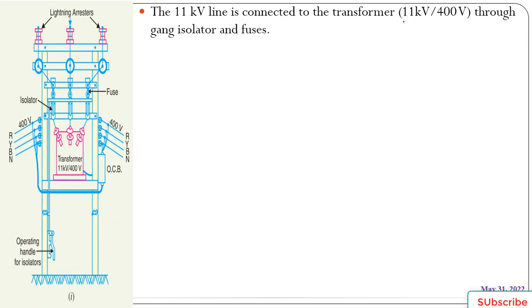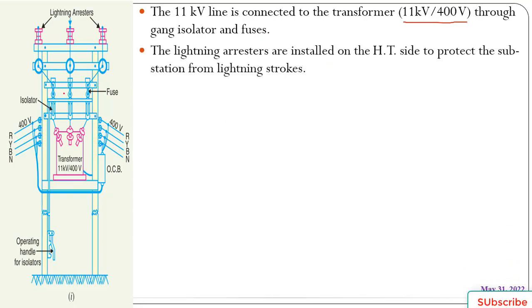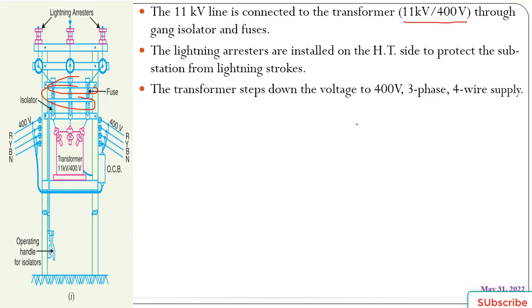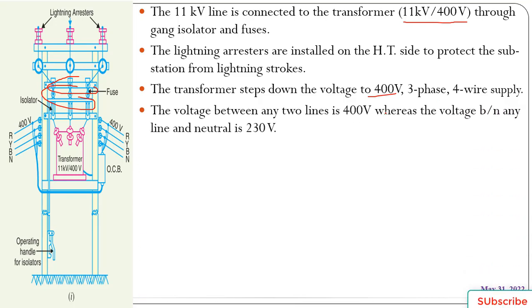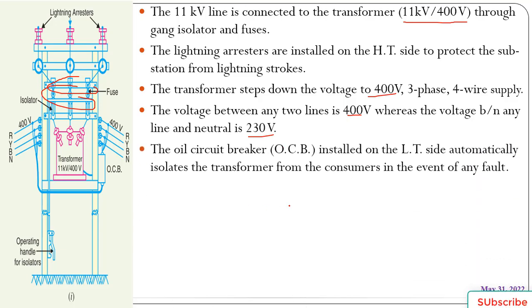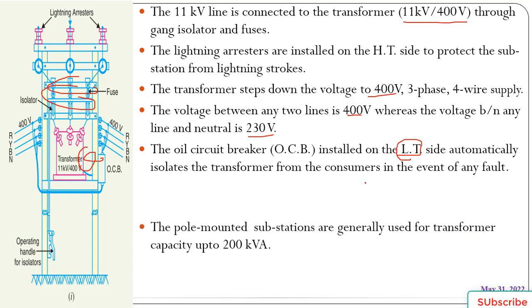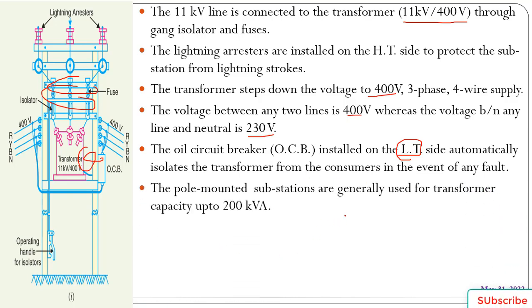The 11 kV line is connected to the transformer, 11 kV to 400 V, through a gang isolator and fuses. The transformer steps down the voltage to 400 volt 3 phase, 4 wire supply. The voltage between any two lines is 400 V and between any line and the neutral it is 230 volt. The oil circuit breaker installed on the low tension side automatically isolates the transformer from the consumer in the event of any fault.